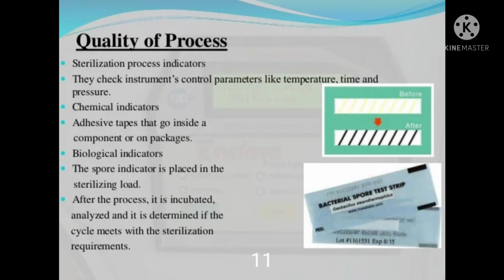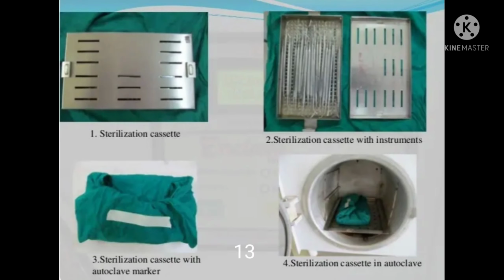To know whether the autoclave process is proper or not, we use quality of process checks. These are basically sterilization process indicators. They check control parameters like temperature, time and pressure. There are chemical indicators, adhesive tapes that go inside a component or on the package. There are biological indicators: a spore indicator is placed in the sterilizing load. After the process, it is incubated, analyzed, and it is determined whether the cycle meets sterilization. There are different types of indicator labels available in the market. The class B indicators are also available. They change color when the autoclaving is proper, and we come to know whether the autoclaving is correct or not.